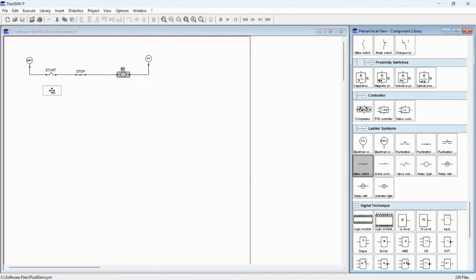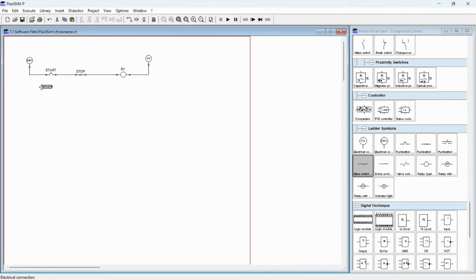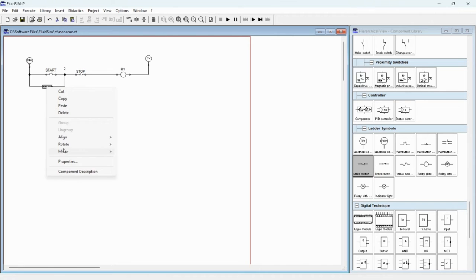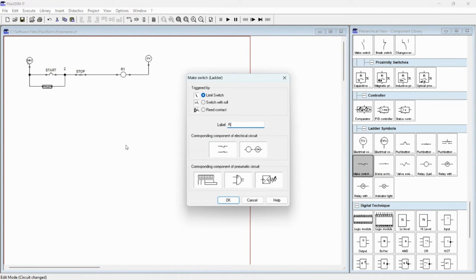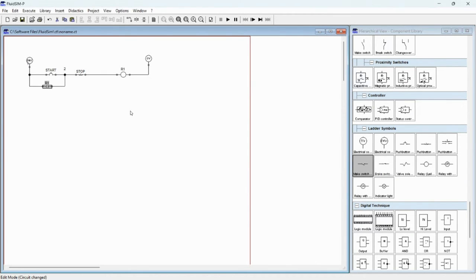Drag and drop the make switch and connect to the power side — this way you can latch the start button. Now we have to name it as R1. We are using the normally open contact from the relay. Now when you press this button, the power flows and the relay will start. After the relay is on, you will get a latch and keep the circuit on.